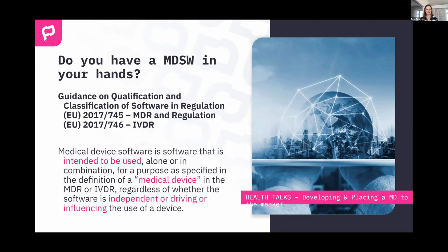Just a few examples. Not all software that is used in the healthcare business, for example, is qualified as a medical device. One example is just a simple search. If you retrieve some records and you're matching records against different criteria, it's not medical device software. It's normal library software. But if you use basically the same function with the intention to process or somehow analyze, create or modify medical information, then the software is governed by the medical intended purpose, thus going to this medical device software category.